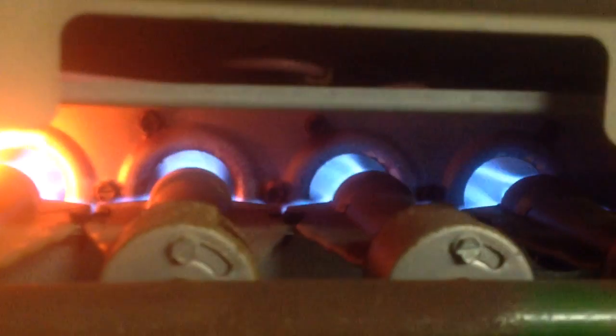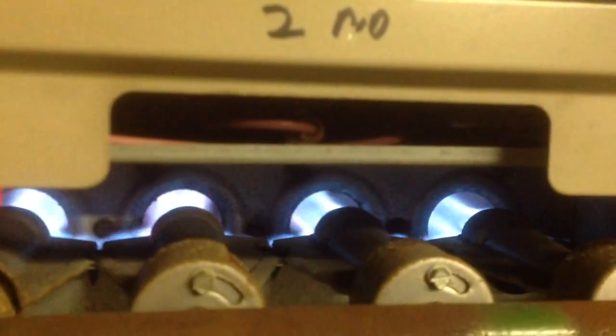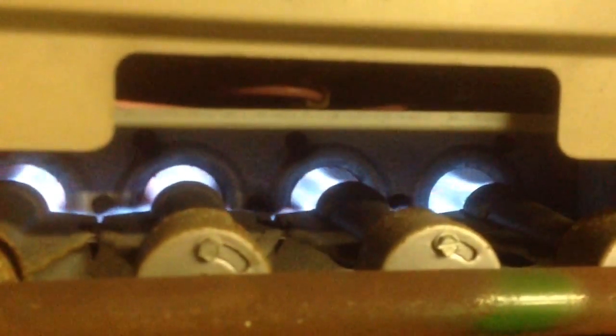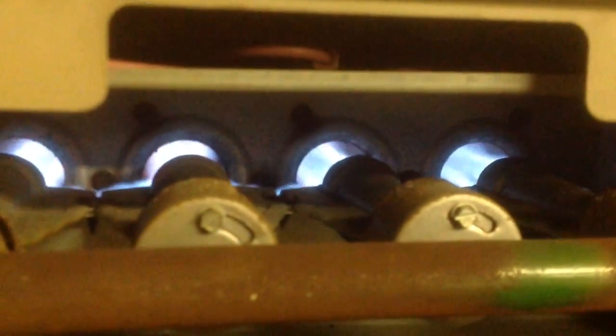There we go, the flames shot out. Those flames coming out were a little too far. But what you want to do is watch the burners. When that fan comes on, if you have any fluttering on the flames, you have a bad heat exchanger. They should look the same whether the fan's on or off, because that fan will blow air into the exchanger.